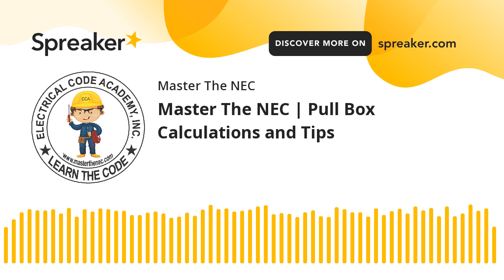Okay, so pretty straightforward. Now LBs are a little different, LRs a little different, but you're using angle calculations. We'd be using the values for 314.28(A)(2) for those. Okay, so we'll talk about that in a second. All right, so we've just done everything that's associated with the straight pull. Now, the confusion will start when it comes to angle pulls, U-pulls, or splices.